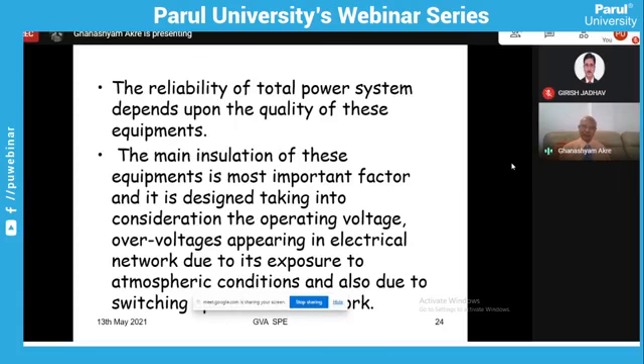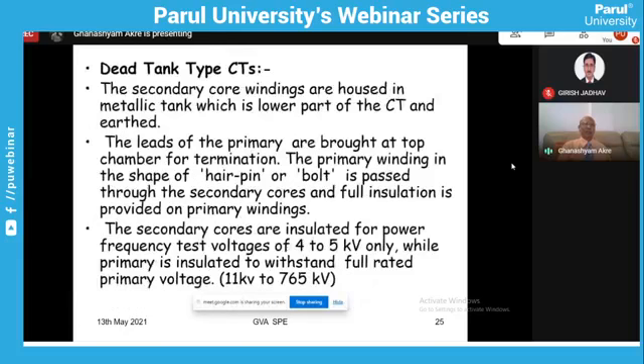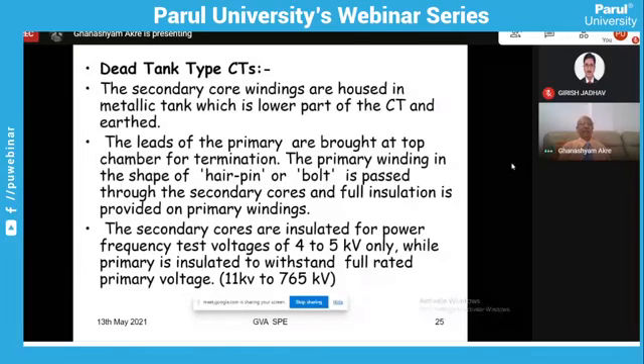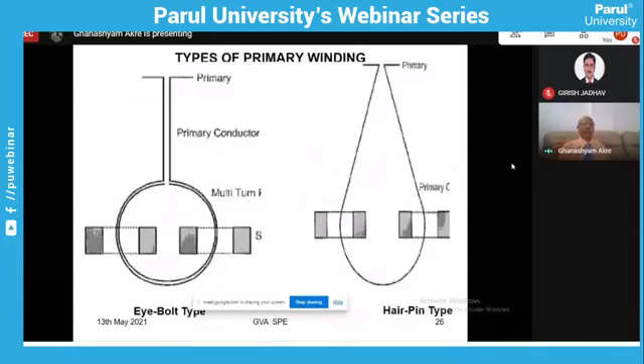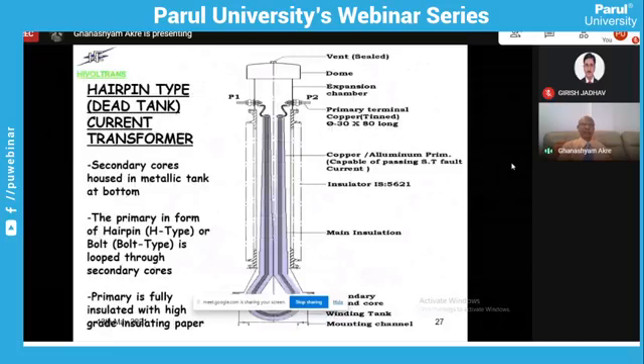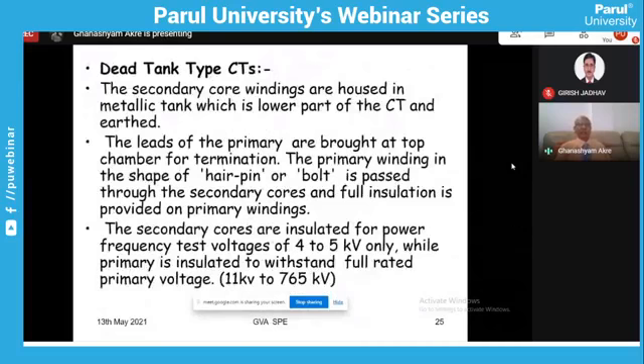And that is why the insulation is done in such a way that it will accept all the stresses produced because of these different disturbances, voltages appearing in the instrument section, in the transmission section. We'll just look at the differences. What is the dead tank type CT and what is the live tank CT? You can see the dead tank CT. I will show the first figure here.